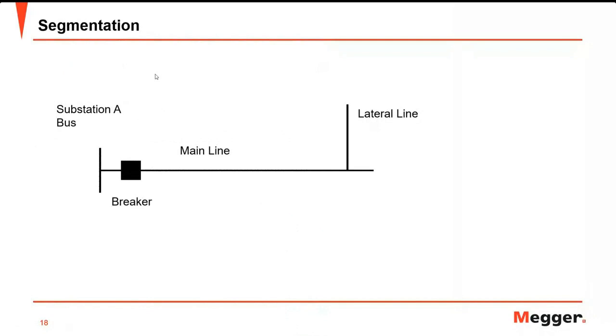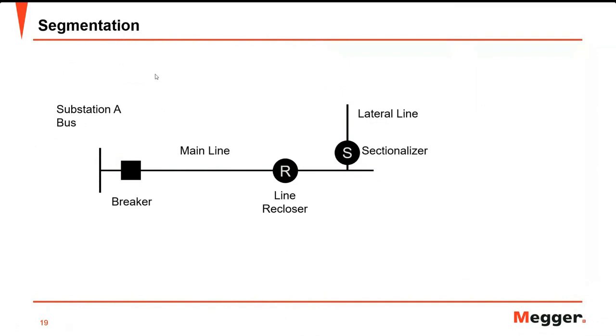Segmentation: if there's a fault at a lateral line, the breaker trips and the whole feeder loses power. If you add a recloser in the main line and the same fault occurs, only a portion of the main line and the lateral line loses power. This is beneficial to the utility in terms of reliability indicators and energy sales.